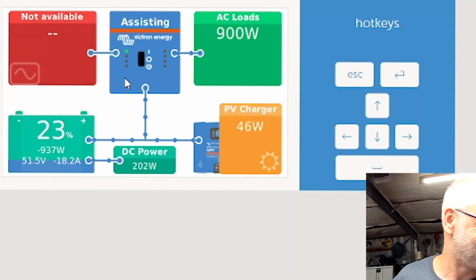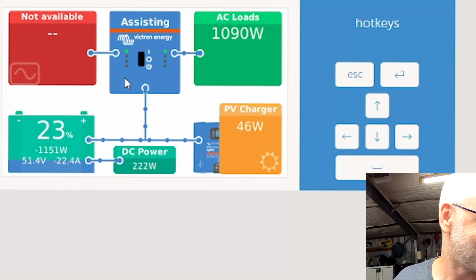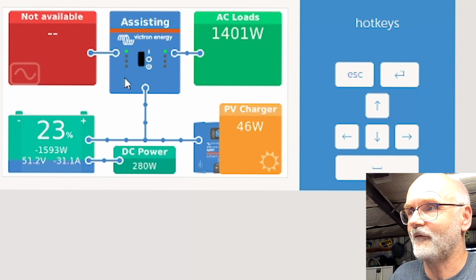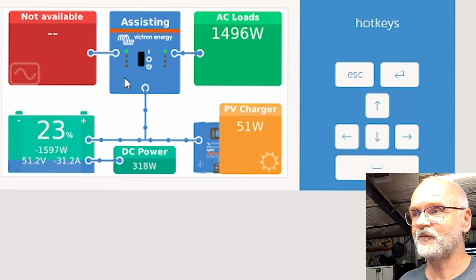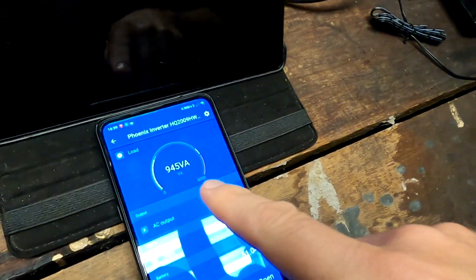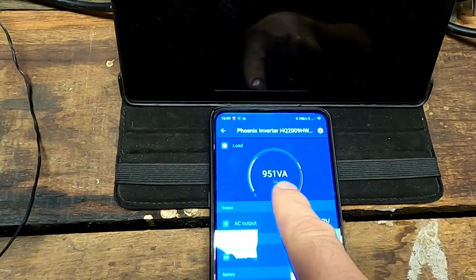Okay, now we are back to normal. It is still assisting, let's crank it up to 21 amps. This is full power from my power supply here - 1.5 kilowatts. And here you can see we are pulling 940 watts from the Phoenix. Something is not working as it's supposed to be, because I told the Multiplus to assist above 1 amp.